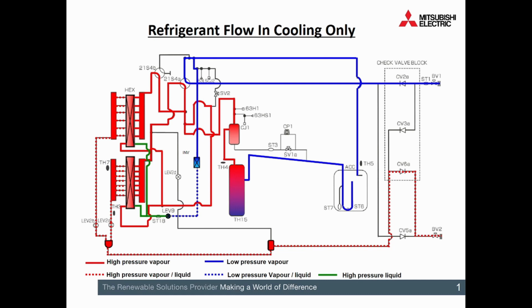And the other one is just literally a way of measuring the actual pressure on the high side. From there, that refrigerant is passing off and we're going to come up to our reversing valves. So we're using reversing valves to load up that outdoor coil as well. In this situation, obviously they're both in the off position as we're doing cooling. And we send that refrigerant through the outdoor coil.